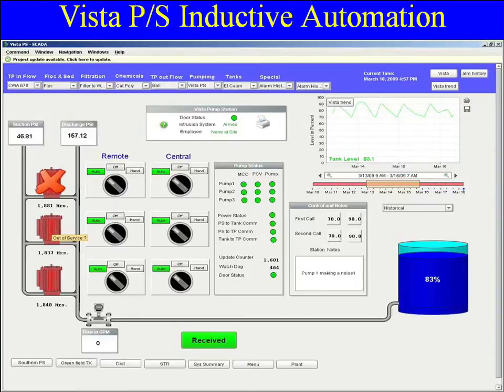Probably one of the nicest functions of the product being web-deployed is that I can now build screens in more than one location. There are five instrumentation and control techs, and we can all concurrently develop screens at the same time — no longer are we limited to one person working on the development box at a time. Because it's web-deployed, any SCADA computer can actually develop screens.